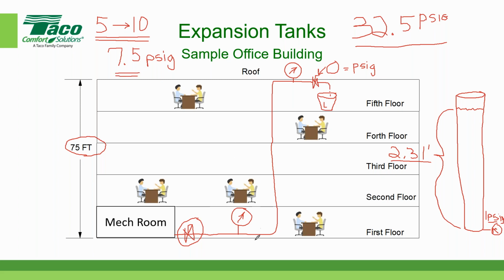If I have 7.5 at the top, what is my pounds per square inch at the bottom, where I have my gauge down here? If I've increased the pressure until I get 7.5 at the top, what's my new pressure at the bottom? Mario jumped in quickly today. He said 40, so did Chris. 40 is correct. So you guys get it. 40 PSIG. How did I come up with that? I simply took the pressure I wanted, which was 7.5 at the top, and added that to the pressure that's already at the bottom: 32.5 plus 7.5 is 40 PSIG. That's why I picked 7.5. I wanted it to come out simple, easy math. So that's my minimum pressure that I want at the bottom of the building. It's also the fill pressure. It's also the pre-charge on the air side of the bladder of the expansion tank.